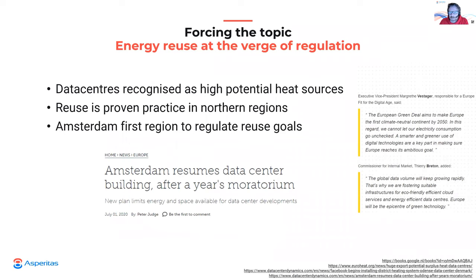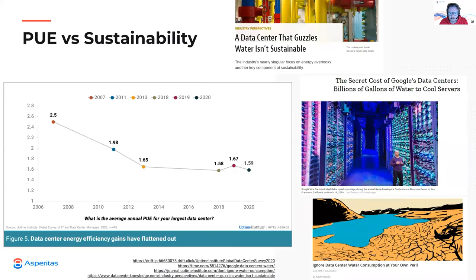And this results in many areas now starting to regulate data centers and the creation of legislation around energy and the reuse of heat. Amsterdam is a front runner in policy making and implemented a full data center moratorium in 2019 to allow a full reassessment of the possibilities, which has resulted in the first solid regulations for data center development with a focus on reuse. These regulations come on top of the already ambitious existing regulations, which require new data center developments to design for a PUE of 1.2. But also PUE is under evaluation.